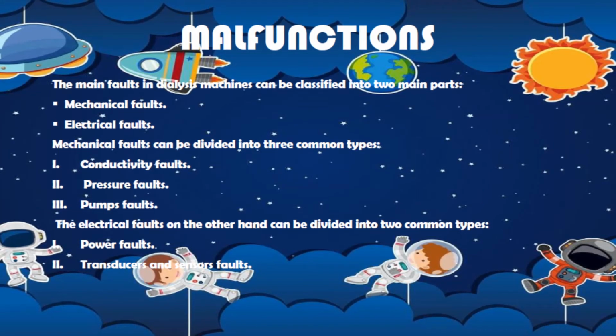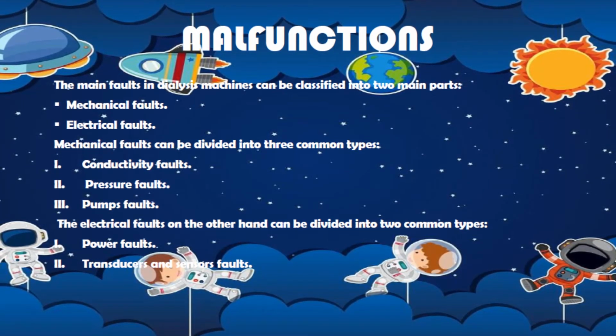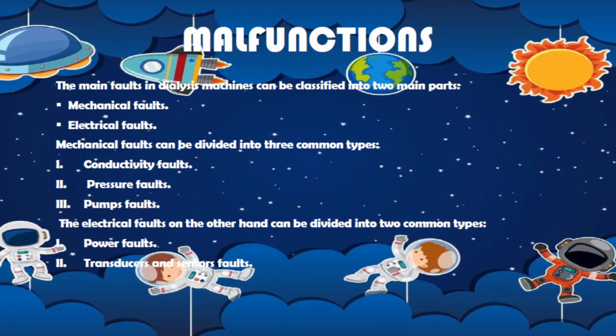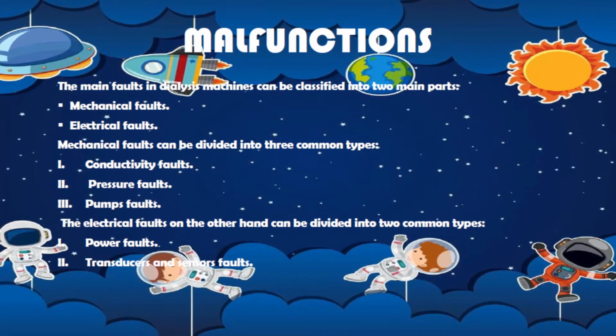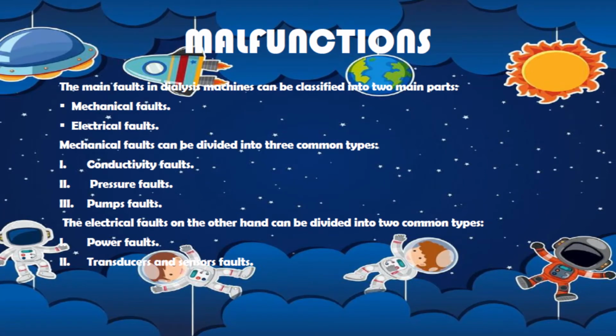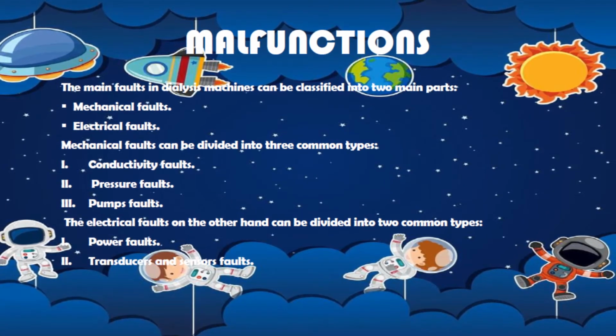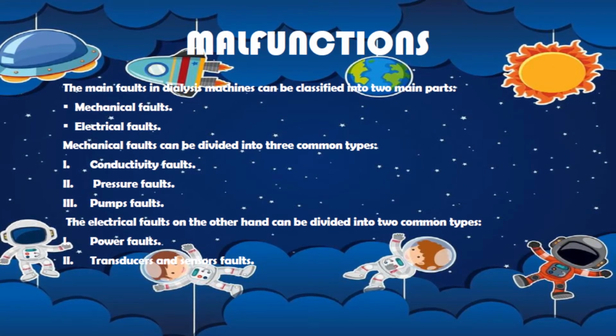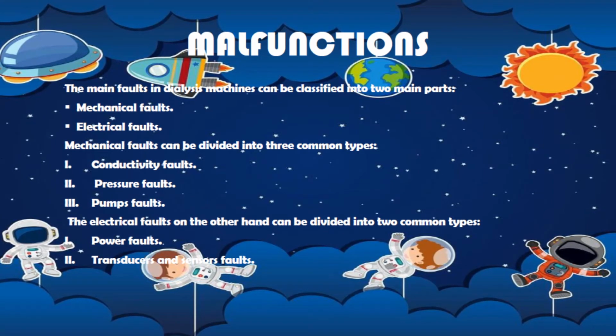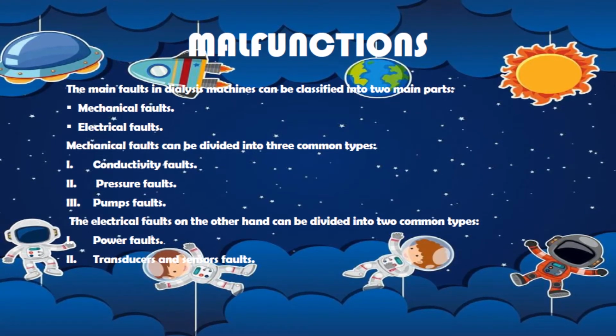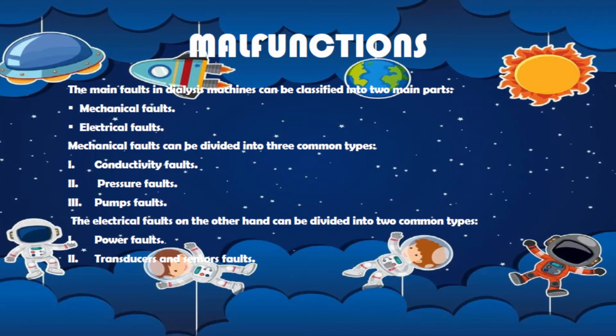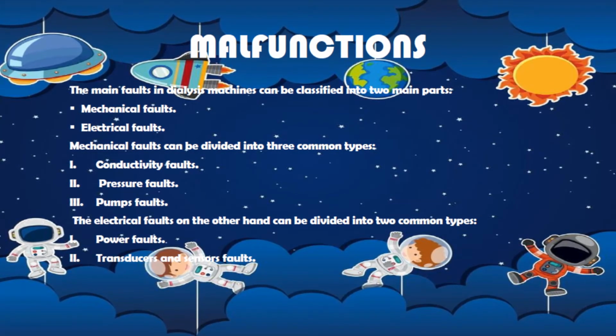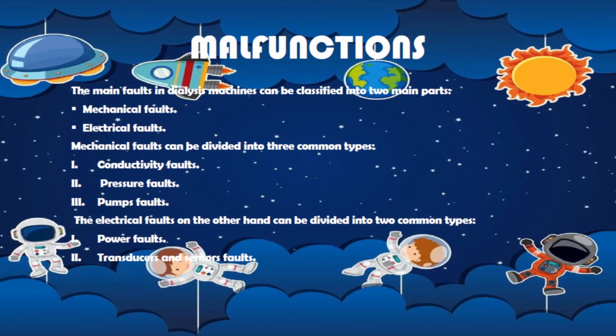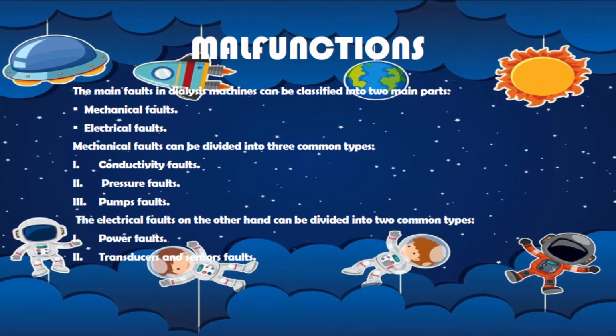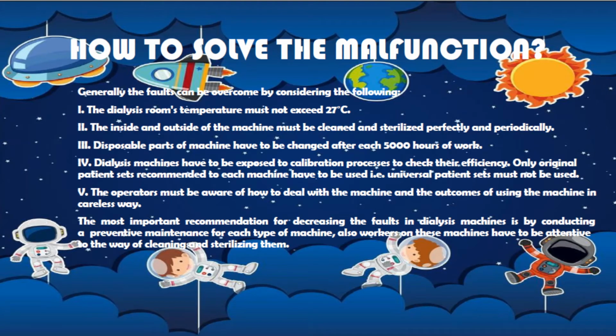There will be a few malfunctions with the dialysis machine. The main faults in a dialysis machine can be classified into two main parts. First, mechanical faults. Second, electrical faults. Mechanical faults can be divided into three common types: conductivity faults, pressure faults, and pump faults. The electrical faults, on the other hand, can be divided into two common types: power faults and transducer and sensor faults.